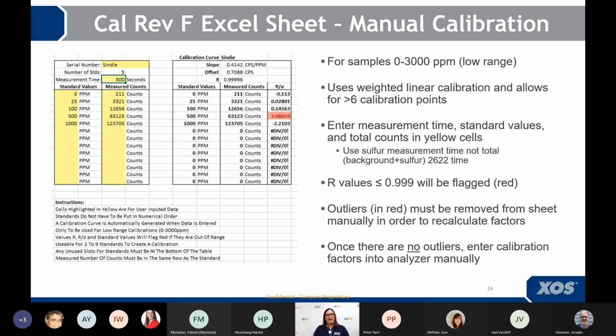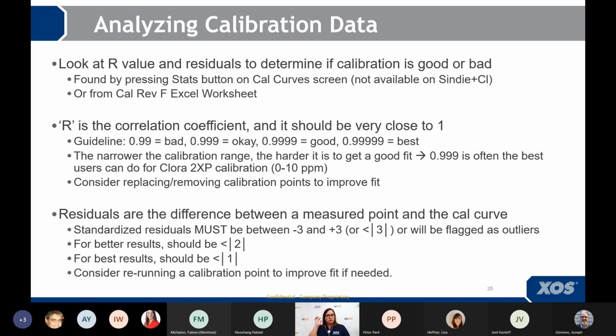But I often get asked, how do I know I have a good calibration? So remember this red outlier here. I'm going to refer to this in the next slide. What you want to do to determine if you have a good calibration is you want to look at the R value and look at the residuals to determine if the calibration is good or bad. Okay, you can find it by pressing the stats button on the calibration curve screen. Note that's not available on the Sindie plus Chlorine, so you can get that value from the Cal Rev F worksheet.